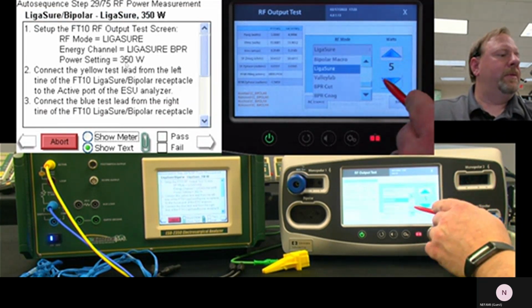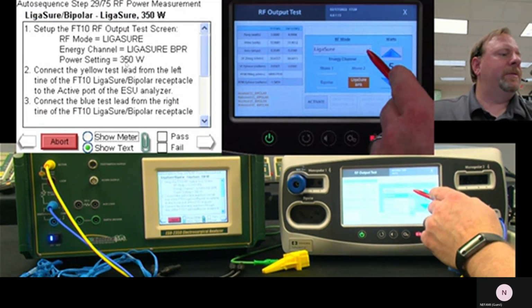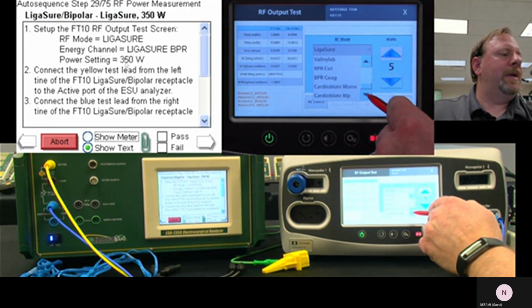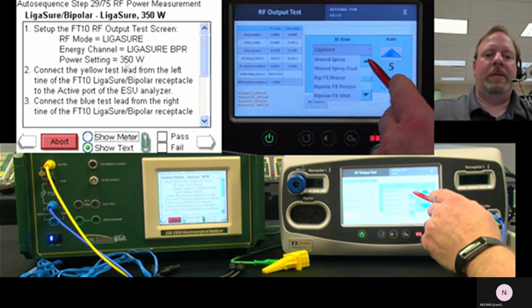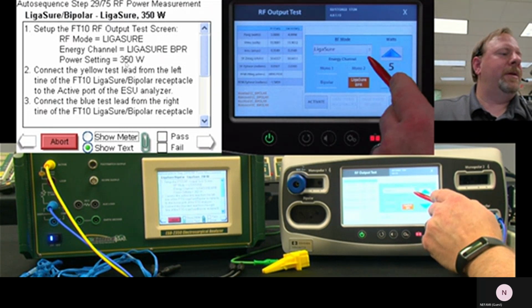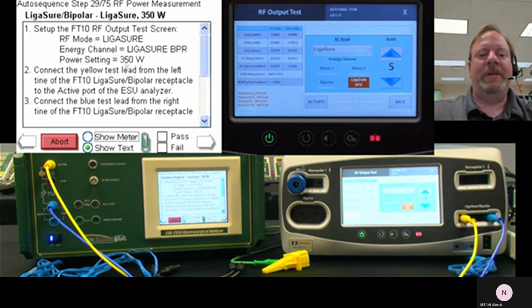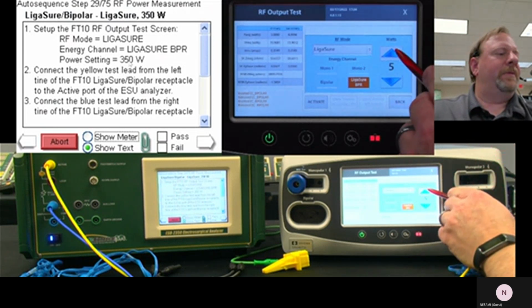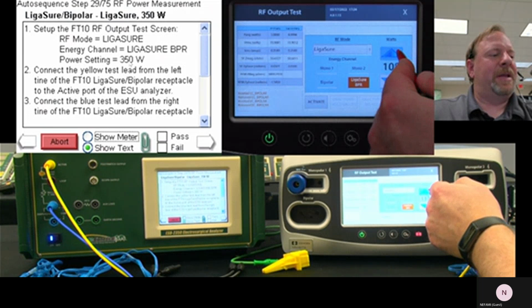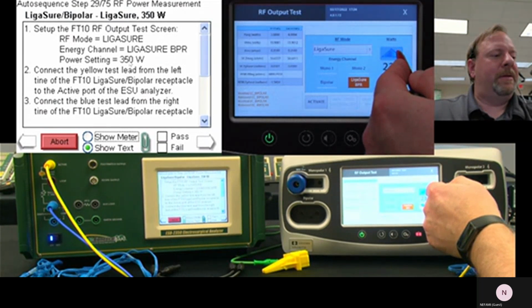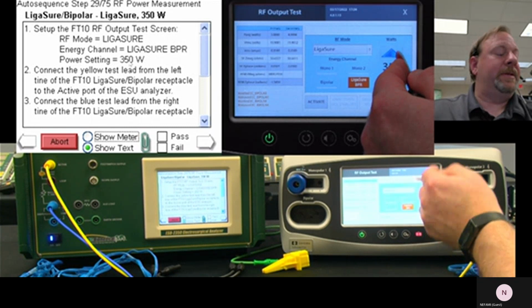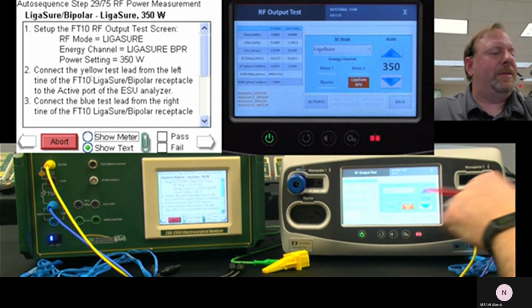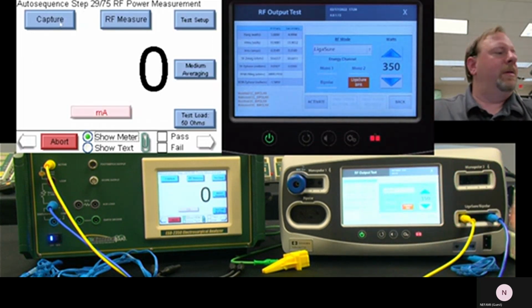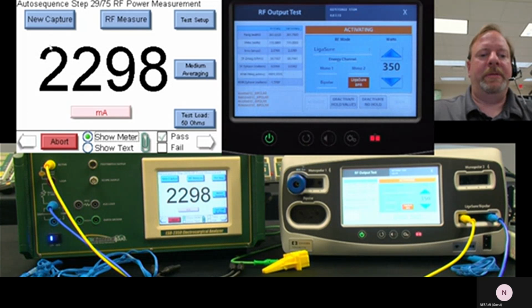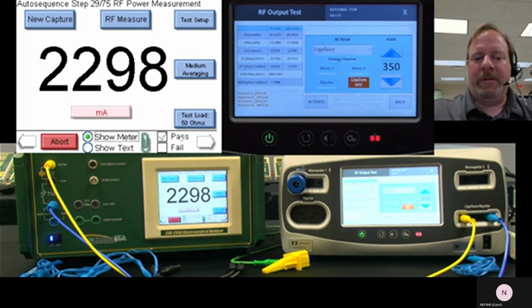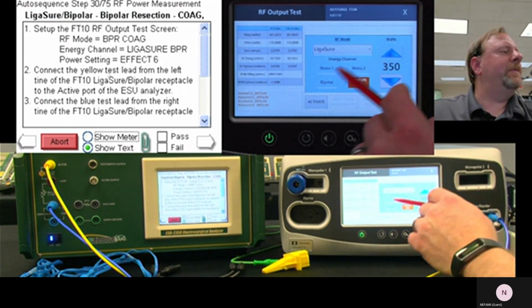LigaSure BPR. That one is somewhere else. I thought it was at the bottom, but I thought wrong. Oh no, RF mode. Sorry. RF mode is LigaSure. I was in the right one. And the channel is BPR. Power setting 350 watts. This is the only Covidien output that is higher than 300 watts, at least that I know of. So 350 watts, yellow to the left, blue to the right. Activate and measure. Capture that. 2200 milliamps, or 2.2 amps if you like.